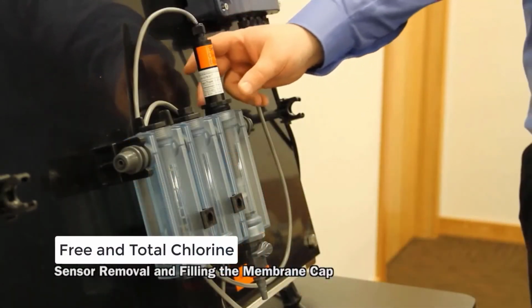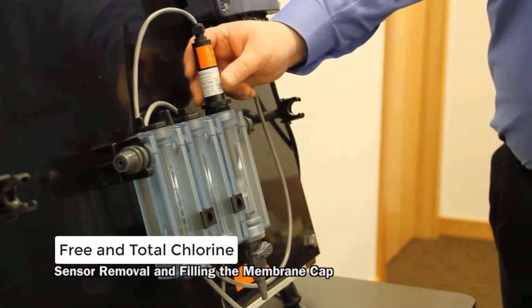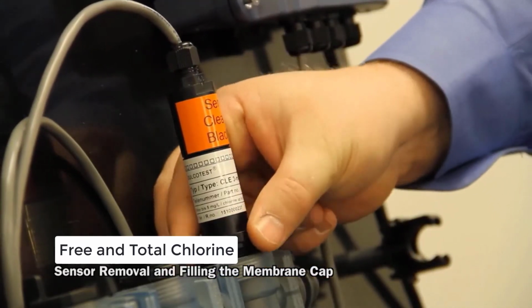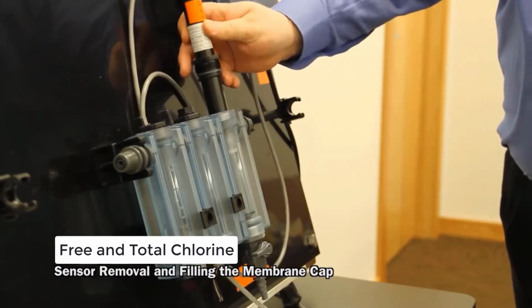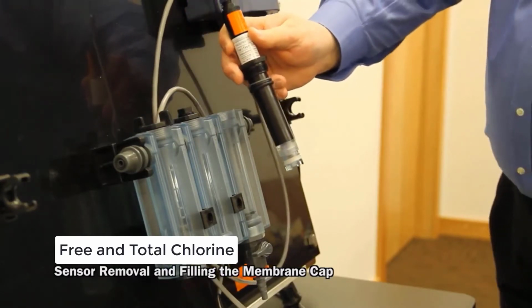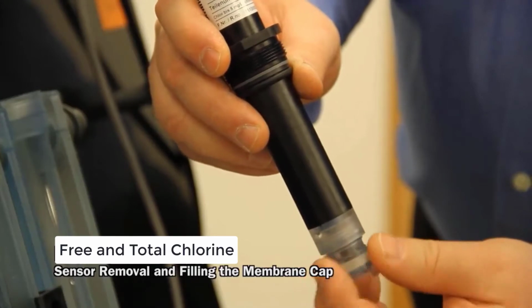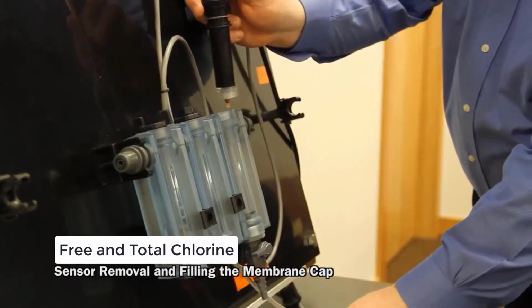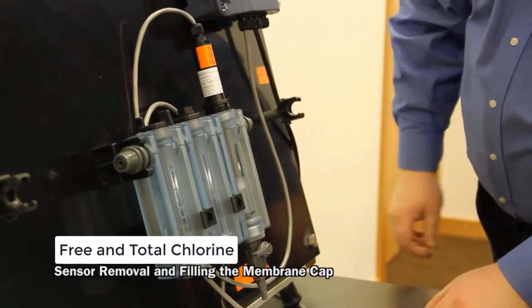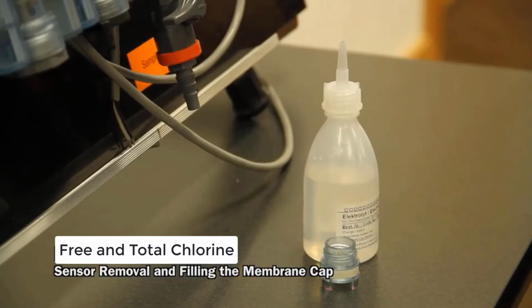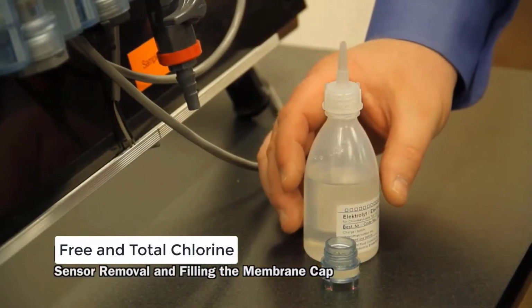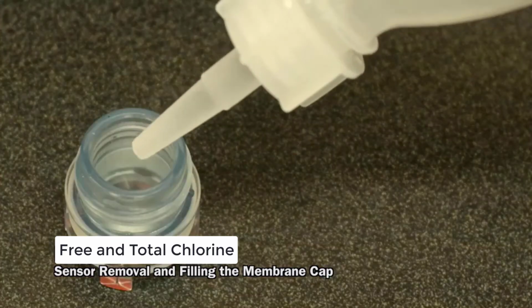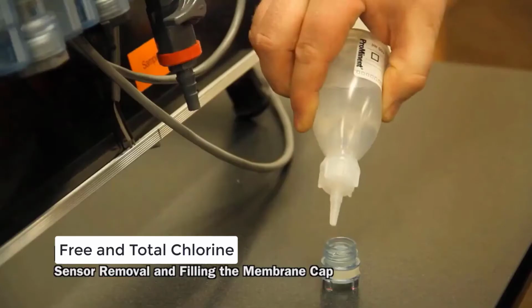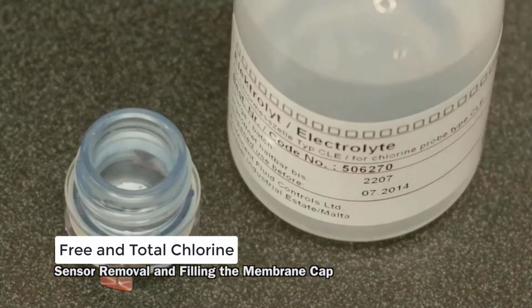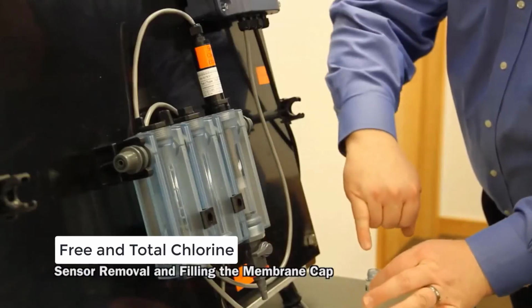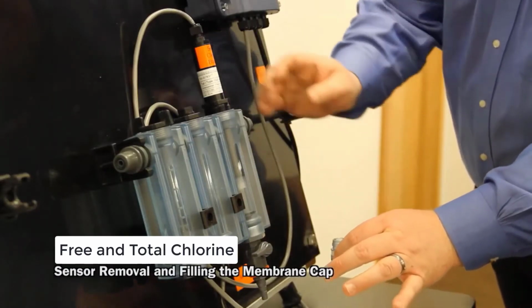So we're going to be sure that we don't have flow in our sample line. Loosen the compression fitting holding the sensor in place. Remove the sensor from its sample cell. Remove the membrane cap. I'm just going to place that there for the time being. Now this particular sensor has a very water-like electrolyte. We're going to fill that cap full. Be sure that there are no air bubbles down where the membrane is inside of the cap.